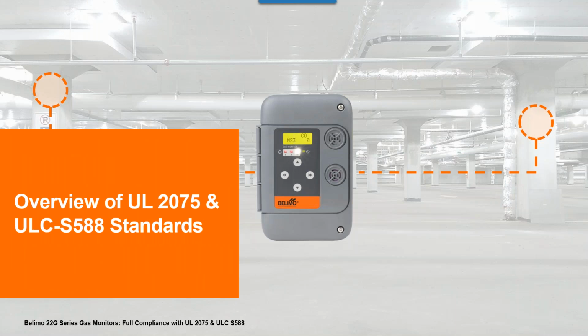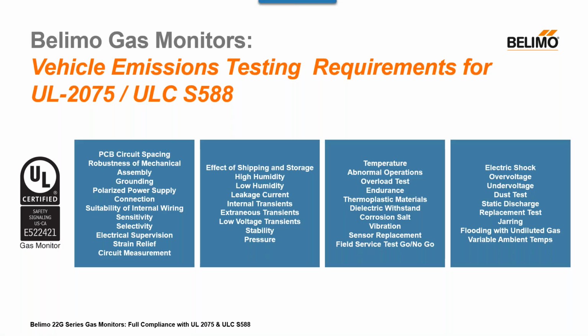Let's delve a little bit deeper into an overview of the UL 2075 and S588 standards. Belimo gas monitors go through a lot of third-party testing for performance, reliability, and safety in order to qualify for UL 2075. This is how we can count on Belimo's gas monitors to protect life and safety in these applications. The Belimo testing, certification, and listing are directly with the original UL design program and carry a very stringent testing program in comparison to other equivalent NRTLs. Here we see a very high-level overview of the stringent testing requirements per 2075 and S588 for Canada. Some examples include low voltage and over voltage testing, grounding, transient testing, endurance of the monitor, vibration, sensor replacement aspects, and effects of shipping and storage.